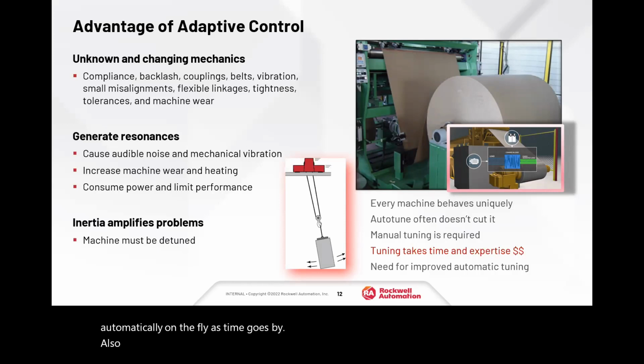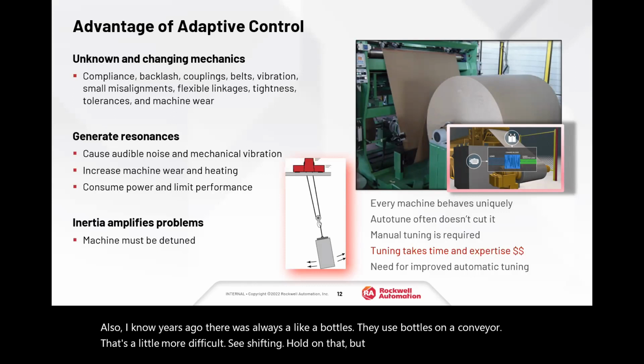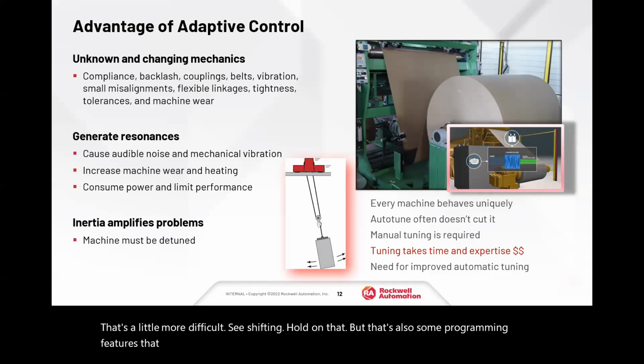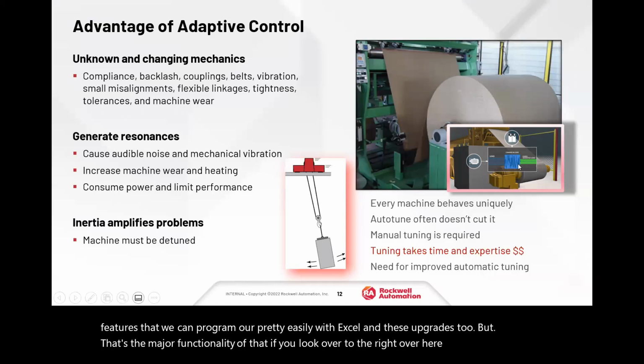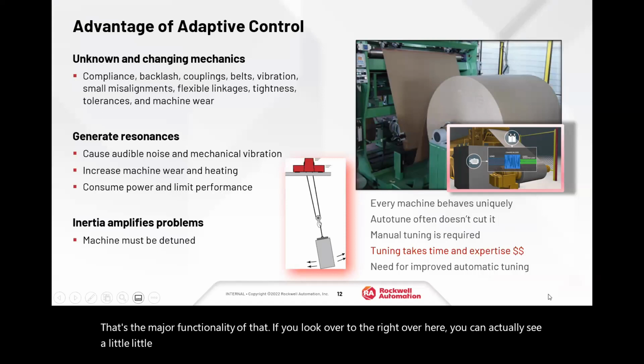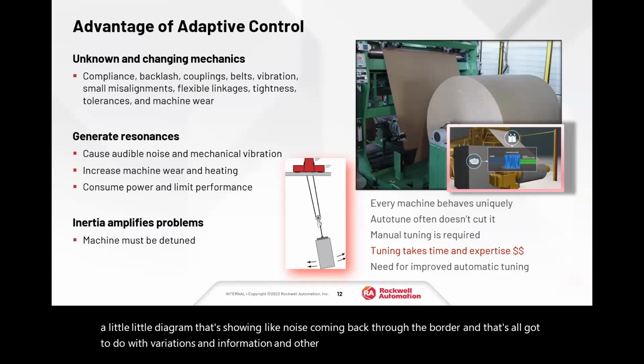Also, I know years ago there were always bottles. They use bottles on a conveyor. That's a little more difficult to see a shifting load on, but that's also some programming features that we can program out pretty easily with accel and decel rates too. But that's the major functionality of that. If you look over to the right, you can see a little diagram that's showing noise coming back from the motor, and that's got to do with variations in amperage and other draw that the drive is seeing at the motor.